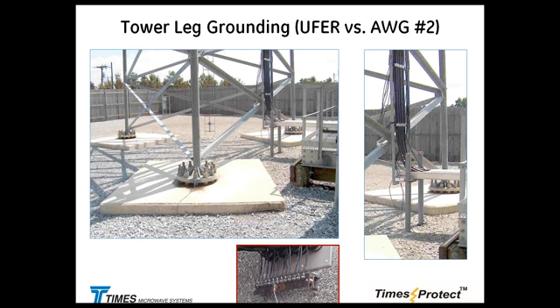Here's an example, not too good a picture, I apologize. Somebody decided to put, probably looks like 250 MCM wire, though I didn't get a description of the exact type. They put the ground lug for the tower leg very high, and here's a little grounding rod, trying to divert the current from the tower leg to that one grounding rod.